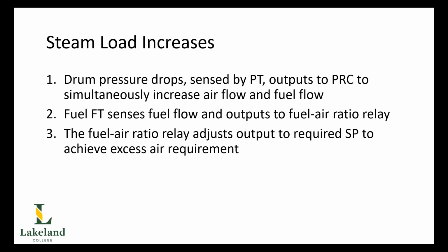The pressure transmitter is going to sense that drop in pressure and output that value to the master pressure recording controller, i.e. the PRC. And the PRC will now generate an output signal to the fuel control valve and through to the modulating relay and down to our air damper drive at the same time, i.e. simultaneously.